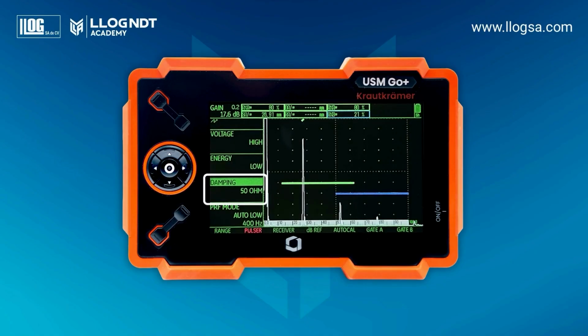Damping controls the number of crystal oscillations after emitting a pulse. It directly affects resolution and sensitivity and can be set between 50 and 1000 ohms. Pulse repetition frequency, or PRF, is the number of pulses emitted per second. For large components, PRF should be lower to allow echoes to return before sending the next pulse.